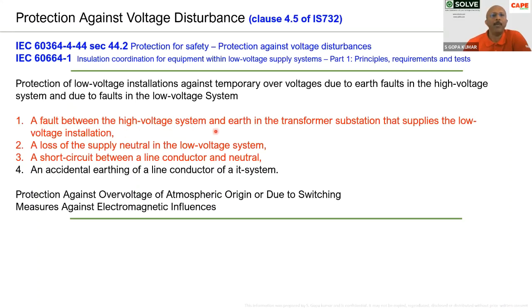A fault between a high voltage system and the earth in the transformer substation that supplies the low voltage installation. That means the fault on the HT side of the transformer, which is going to influence the LT installation. Second one, loss of supply neutral in the low voltage system.